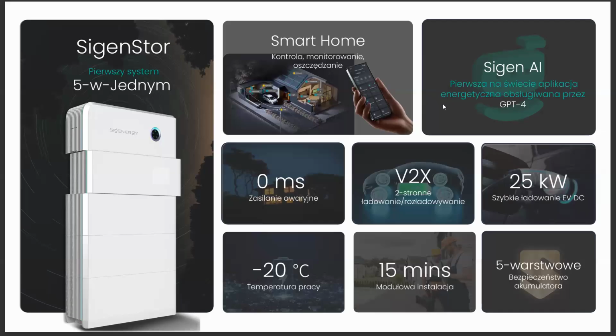Based on 4 pillars. 1. Generation forecast, expected PV production. 2. Weather forecast. 3. Consumption pattern analysis. 4. Hourly electricity prices. The AI makes decisions for intelligent energy arbitrage. For example, if it sees that electricity will be extremely cheap in 2 hours, it may delay battery discharge now and then charge the battery from the grid at a much lower cost. In this way, the system continuously optimizes savings automatically.